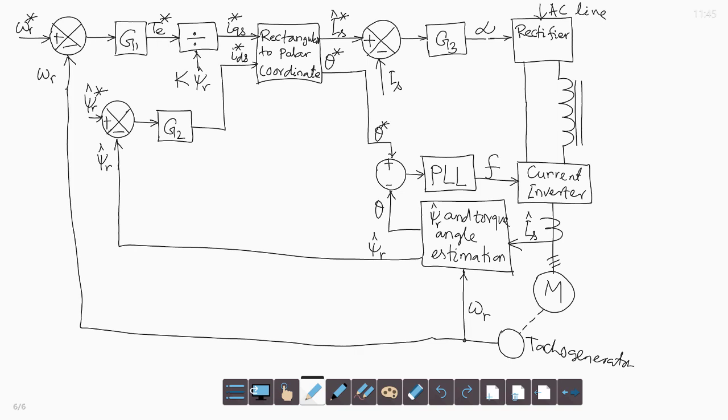And also we have the DC link current sensing, since DC link current ID is multiplied with a constant K1 to generate the stator current IS hat, because stator current IS hat is directly related to DC link current ID. So the actual stator current IS hat is obtained from DC link current after multiplying the constant K1, and this stator current is compared with the reference stator current and goes to control the rectifier.